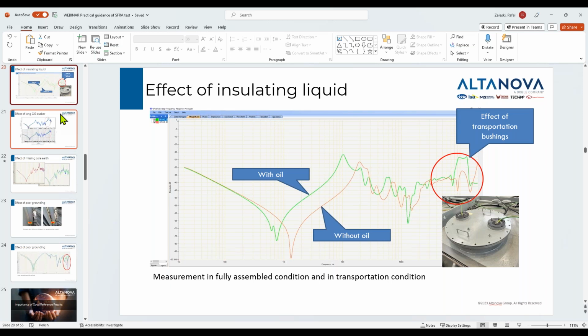You might be potentially right, because this measurement was not made by me, so I don't know exactly. It could potentially be that the red one is from the B phase, but it also sometimes happens that the 2 dips, which are typical for the outer limb, join together in some magnetic condition of the core as well. So it is possible, as you just pointed out, that they are not from the same trace, but the main idea is still the same. There is a shift between them. Whether this was exactly the same or not, I should dig out previous presentations to see who actually did this test and check that. I believe it would be the same phase if someone connected these two traces together. Well, thank you for spotting this.